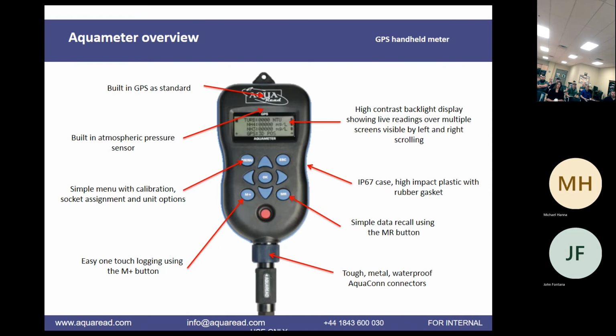We do have a Bluetooth app in development at the moment. I was in two minds whether to include this, because it's kind of old technology, but it's still popular because it's running. You can download the data, up to 10,000 data points, called 4 data sets, and extract that into Excel straight away. All of the compensated data you can pull out. As I said, the meter's got the baro sensor inside, which does all of those compensations, so you don't need a baro logger or anything like that. You can also pull out the raw uncompensated data if you need it for scientific purposes or whatever calculations you want to do.